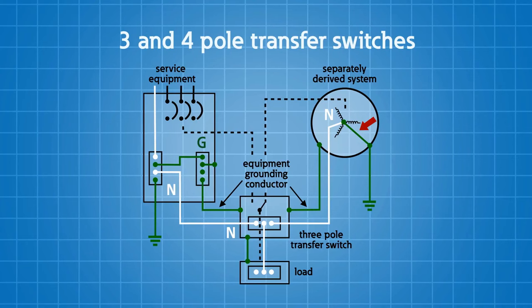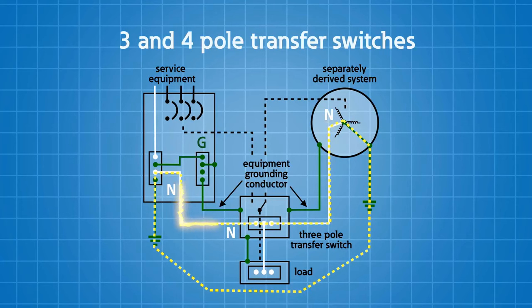But what if I accidentally bonded the neutral to the ground in the generator and I only have a three-pole transfer switch? How do I fix it? Do I have to buy a four-pole transfer switch? Sure, you could. Or you could simply unbond the neutral in the generator. But you must be extremely careful on how you operate a system like this because the return current for the generator neutral will flow back through the other separately derived system or transformer. This is especially important for the electrical workers who will be servicing the equipment.